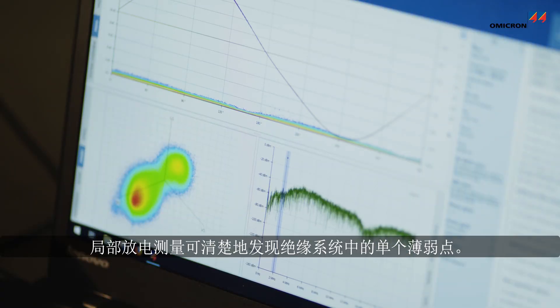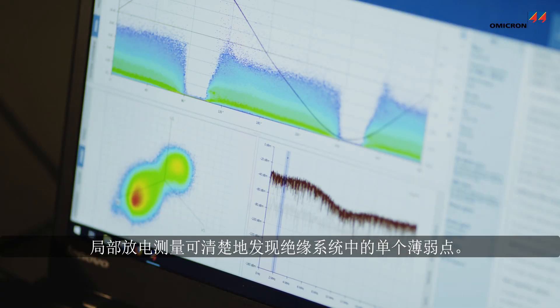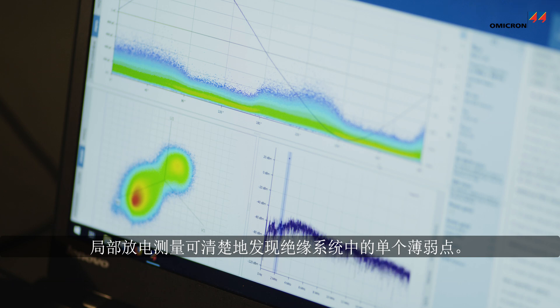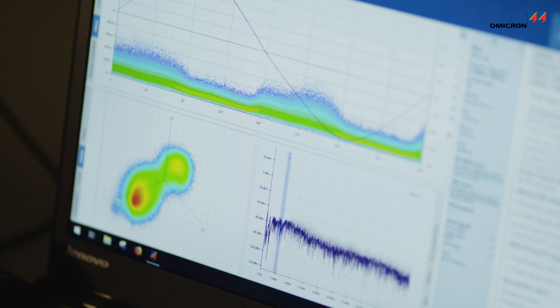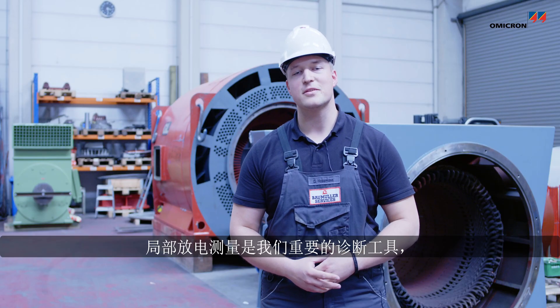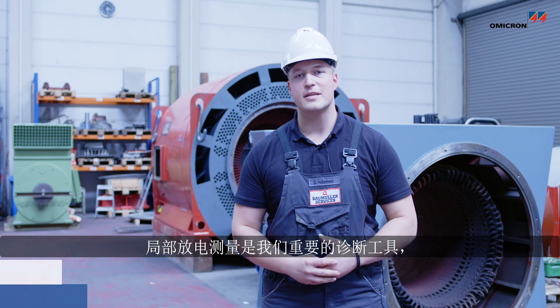PD measurements allow single weak points of the insulation system to be clearly identified. The partial discharge measurement is an important diagnostic tool because it allows us to gain insight into the condition of the machine, detect faults in the insulation, and then initiate maintenance.